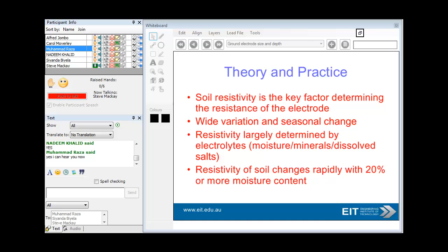Resistivity is a key factor determining the resistance of the electrode. You get a wide variation, and funnily enough it's largely a chemical reaction - moisture, minerals, dissolved salts. The resistivity can change about 20% with more moisture content, so if you've got lots of moisture, you're laughing. But when you do your resistivity calculations, make sure you look at the worst case scenario, the driest part of the year, for example - don't look at the best case, otherwise you won't have very happy clients.